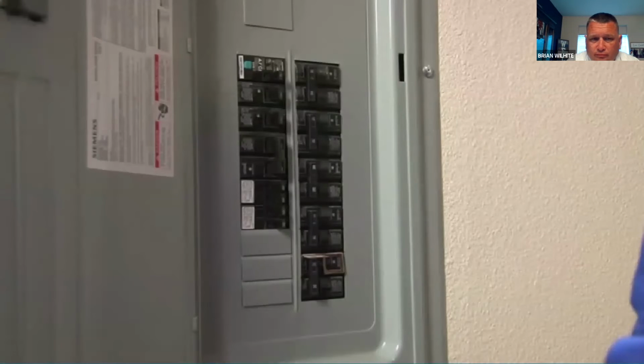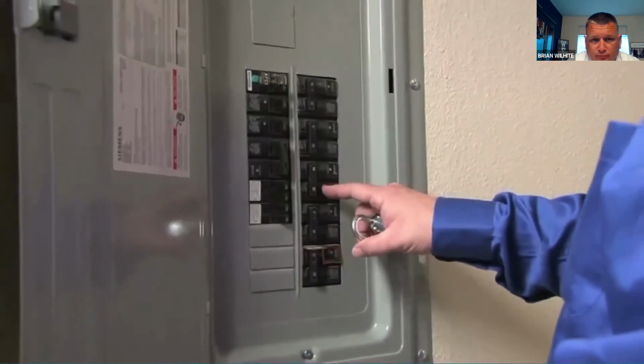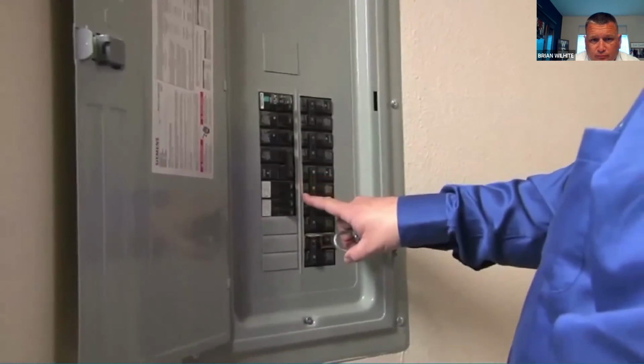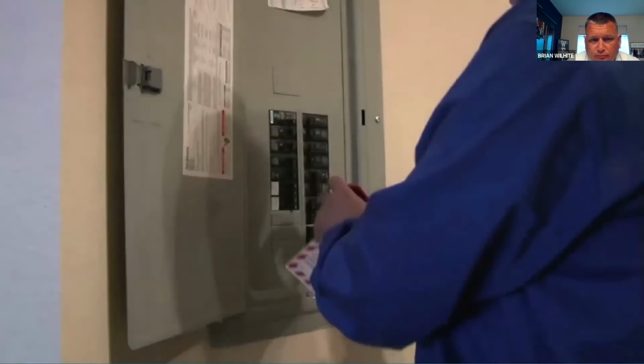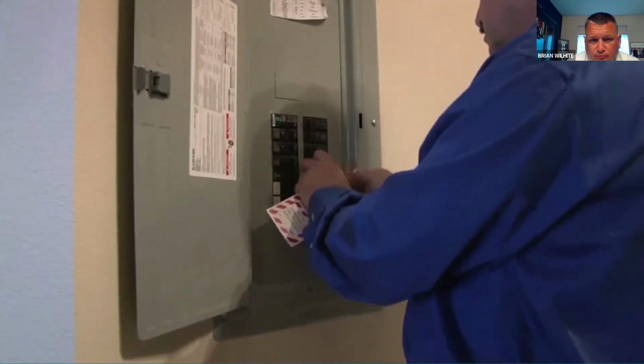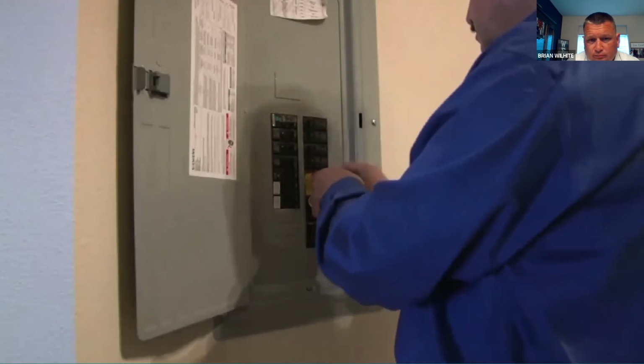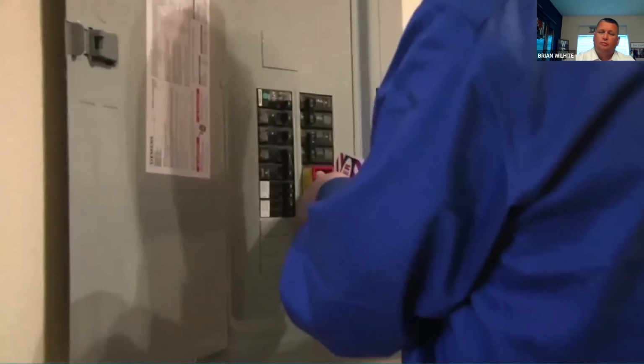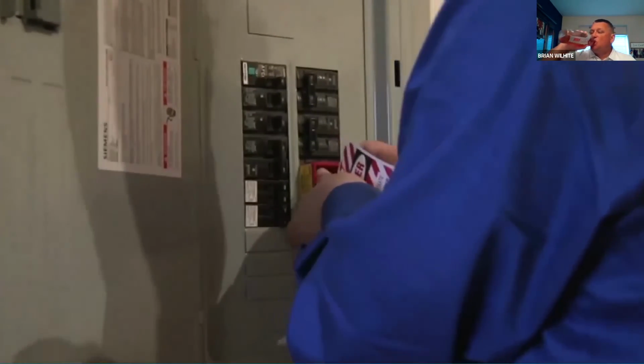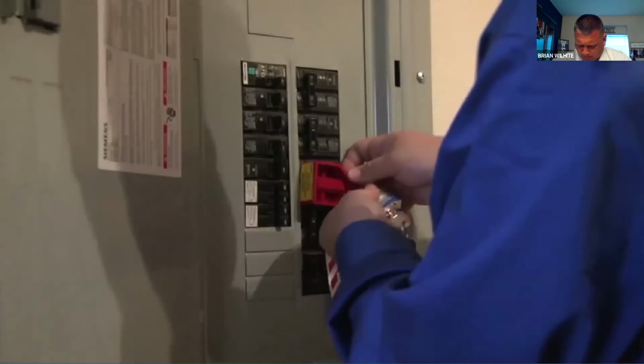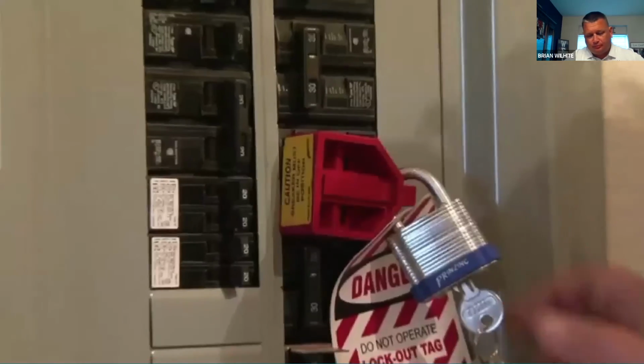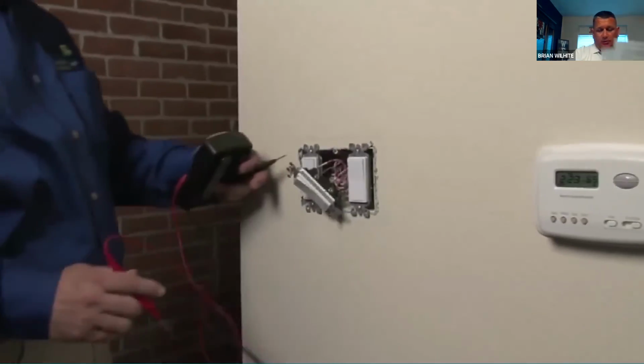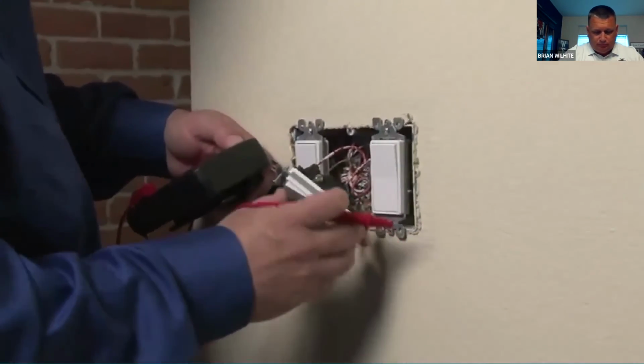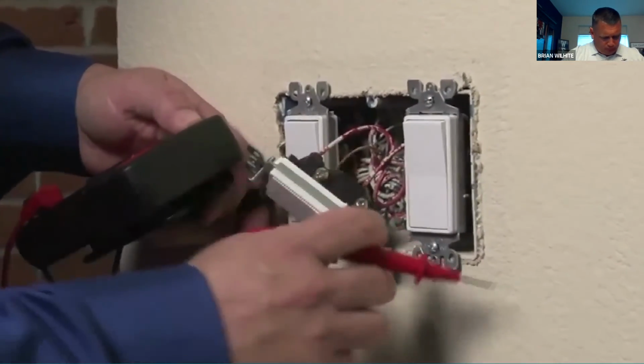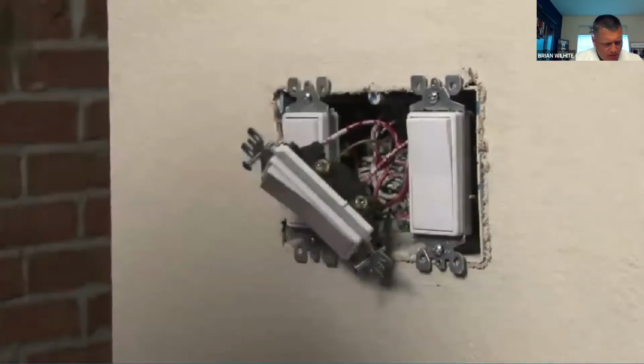So what we're going to do is go to the breaker panel and do a lockout tagout on that breaker. Our technician is now at our service panel, and he identified what breaker it was, and he's going ahead and turning it off. And he's going ahead and putting a lockout tagout on that circuit. The technician's now going to check to make sure we don't have power to the switch, and determine we don't, so we'll go ahead and replace this bad switch.